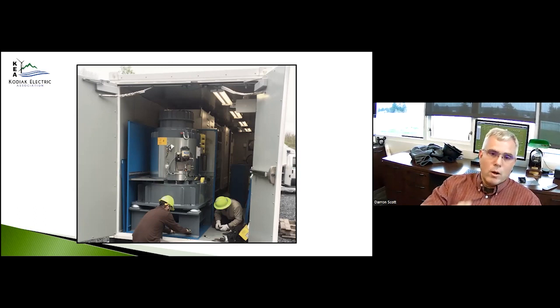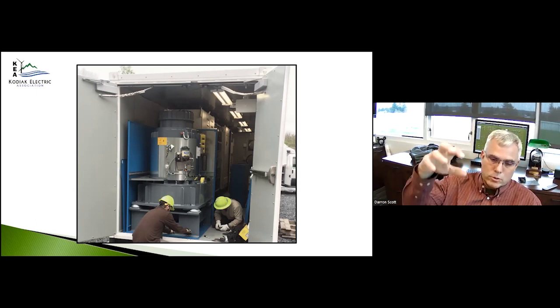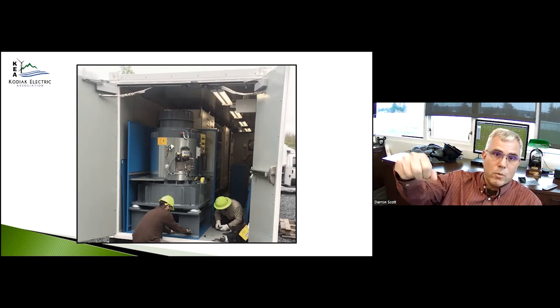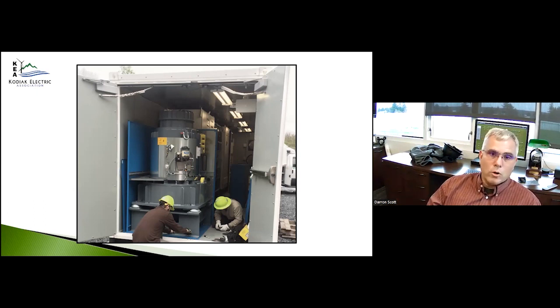Also, we have a large shipping crane on our island that Matson Lines really wanted to put in. It's an electric load - originally going to Anchorage - where you pick the box up using a couple megawatts of power, then drop it back down on the boat, which injects about 1.5 megawatts of power back into the system. Our small grid doing that once - drawing 2 megawatts and putting 1.5 back - wasn't much of a stability problem, but doing that for 8 hours straight, one box after another, would have worn our system out.